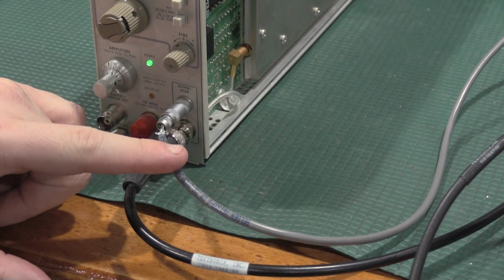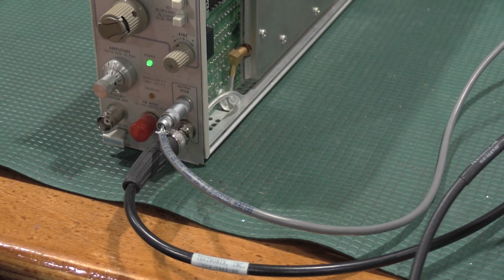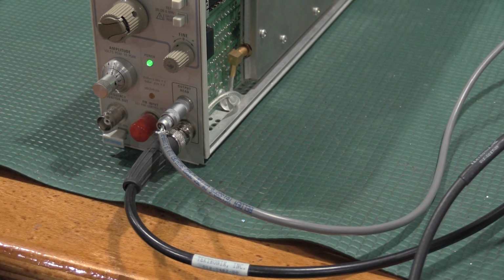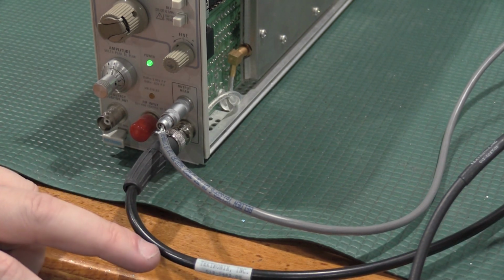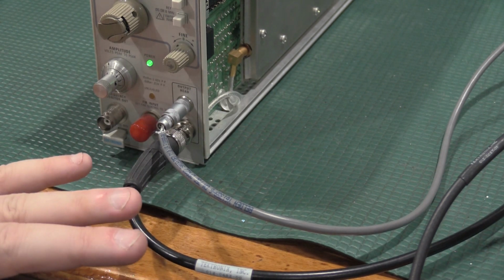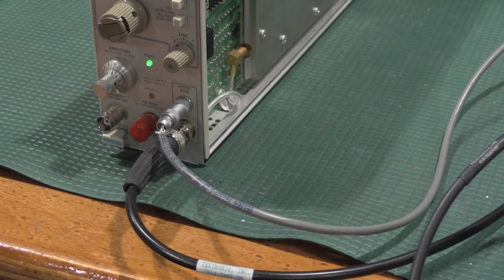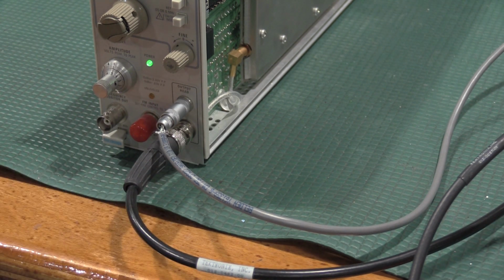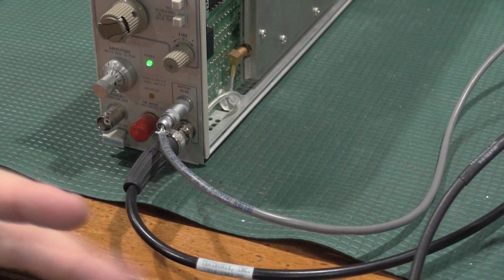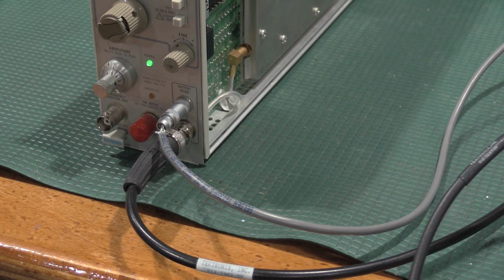So it's a matched length to this cord, and my leveling issues went away. It now levels completely up and down the spectrum, and everything's working. At right around the gigahertz frequency space, I was having impedance matching problems with the cable, which was causing a lot of my headache and frustration. So I'm going to look for another one of these cables. Hopefully I can pull one into the lab, and then I'm going to dedicate it to this head, so the head and the cable will never separate again, and that'll let me use the leveled sine wave generator all the way up. I will also see if I can find one of the Tektronix leveling heads for this and actually have the official Tektronix head, but at the time I picked up the other leveling head, those were not available.